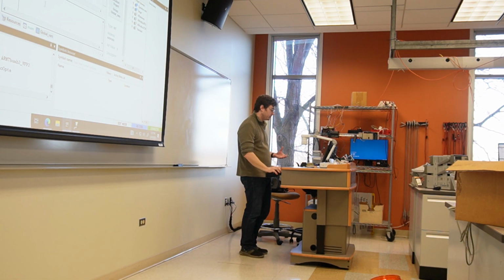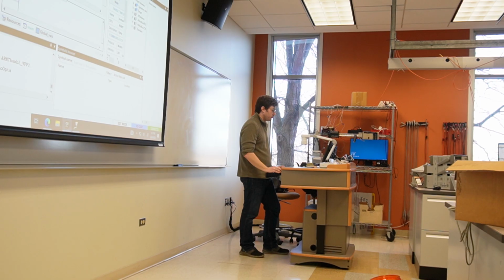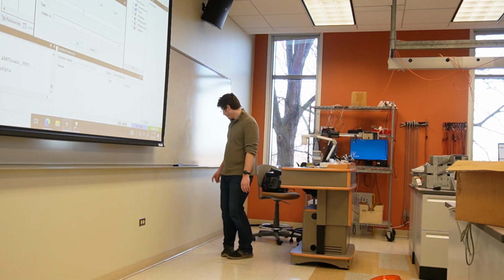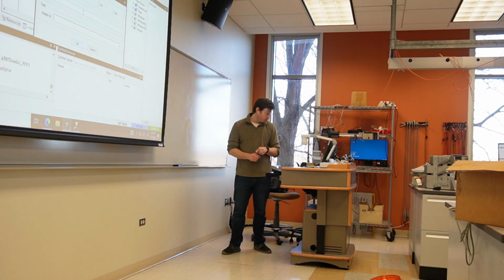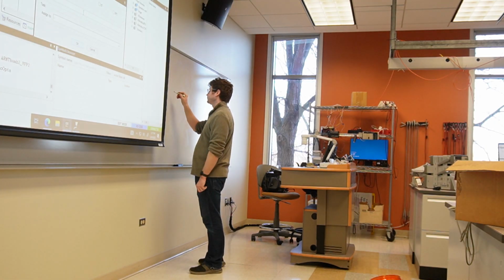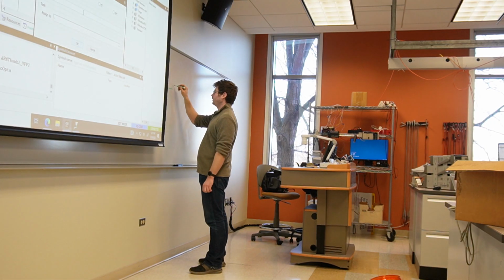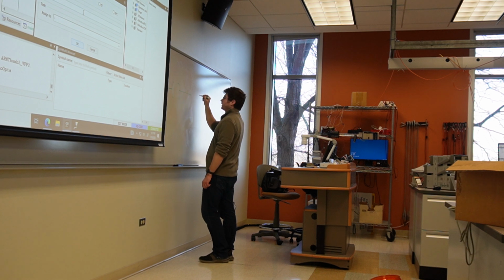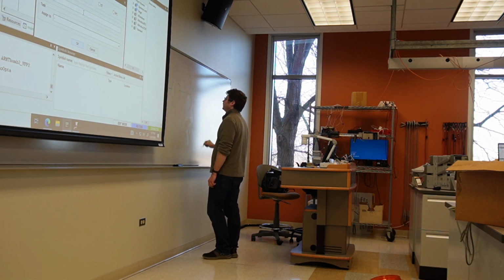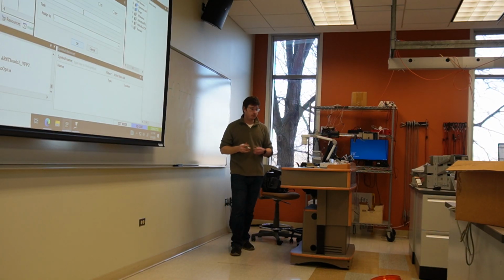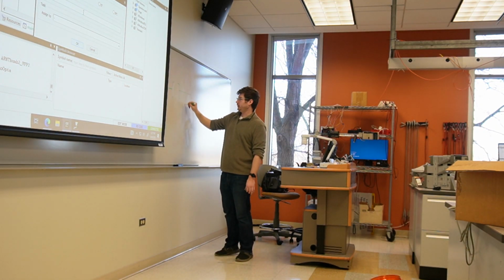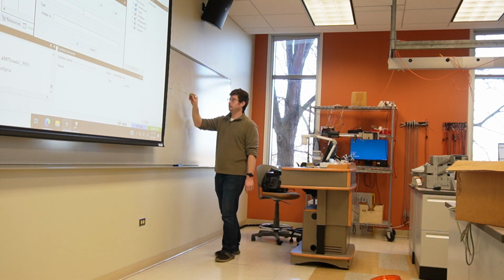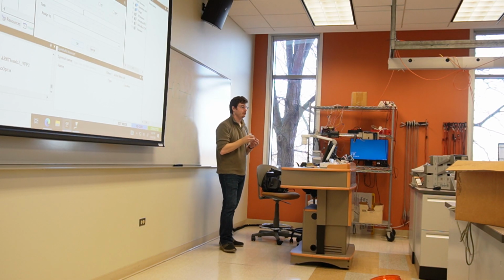We're going to do one more program that I'm going to show you guys how to do. All right, so we're going to create a new program. We're going to go add new program. We're going to create a ladder diagram. Ladder diagram is, as you guys may recall, essentially the programming language-ified version of relay logic, which has contacts denoted in brackets and coils denoted in parentheses, and we can wire them together in different ways, right? We can add a node and have a parallel output here. We could make this normally closed, all that good stuff is ladder logic and ladder diagram.